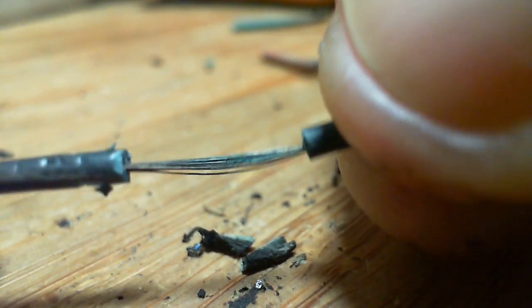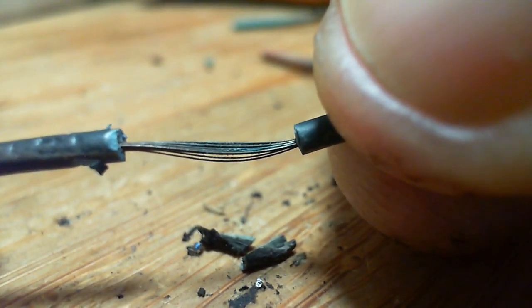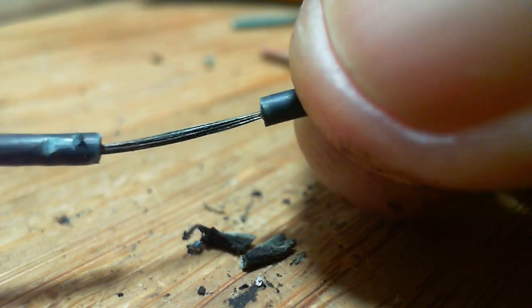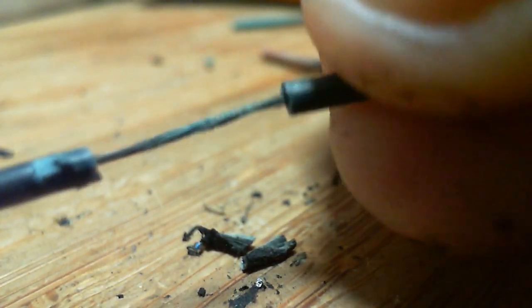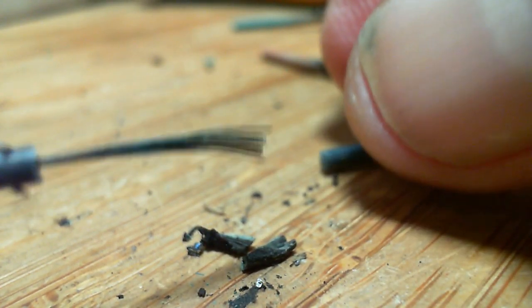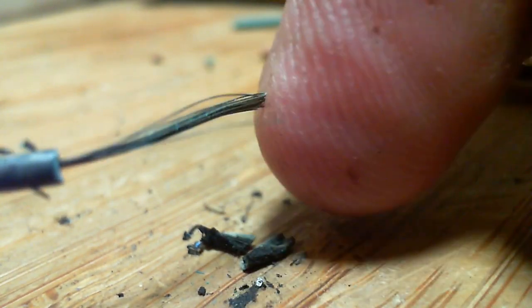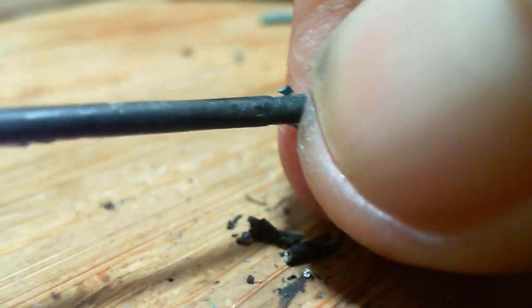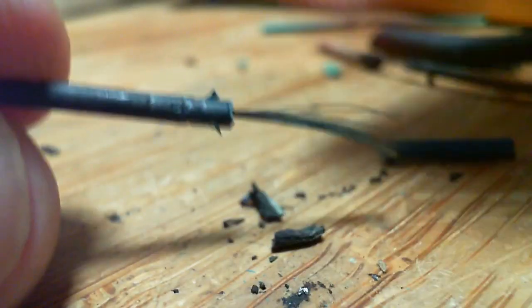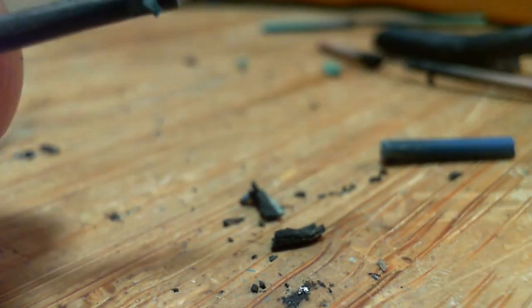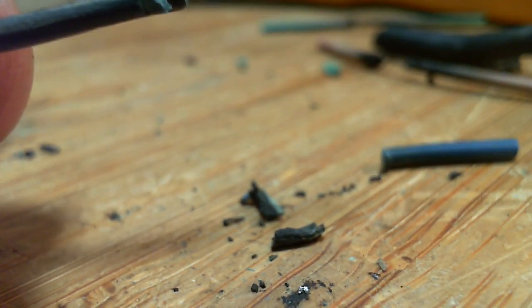There's no broken strands in here. No real signs of overheating from the conductors themselves. I'll pull it right off. So any heat effect, I'll pull the other one. Pull the other one off here. Any heat effect has come from the outside.